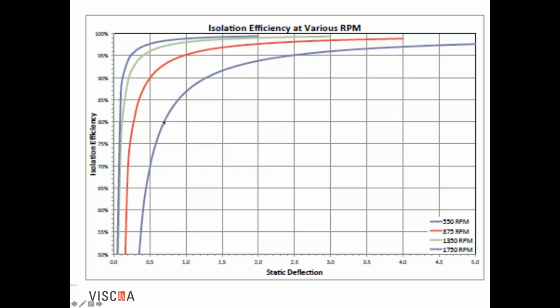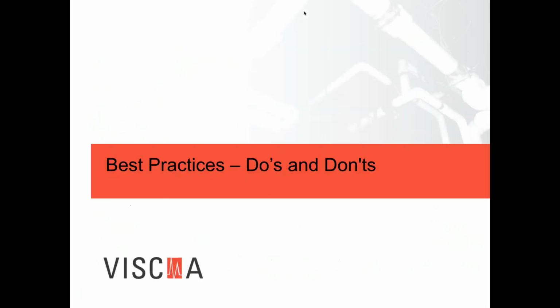Obviously, if you're selecting it down here, first of all, you're selecting it improperly. But now, yes, minus 20%, I dropped 10% in my isolation efficiency. Not a good thing. So all the selections that the manufacturers of VISCMA will be making are up in this range of the curves, such that any minor change from nominal to actual will not affect your isolation efficiency. It's an important point to remember when you're looking for problems, trying to find problems, or just reviewing an installation submittal.